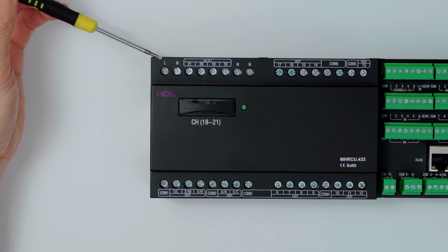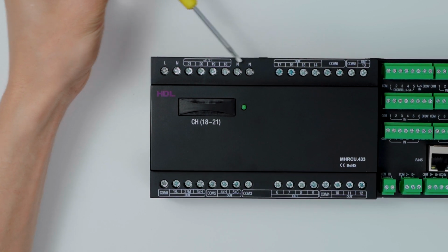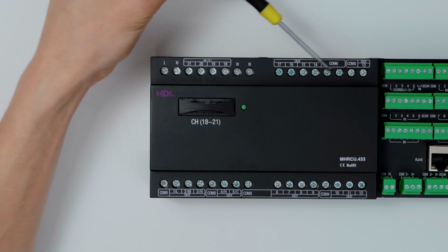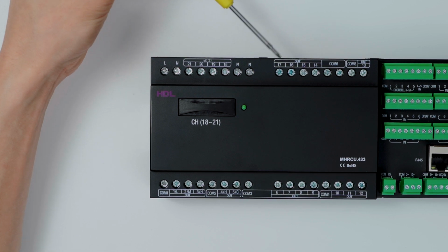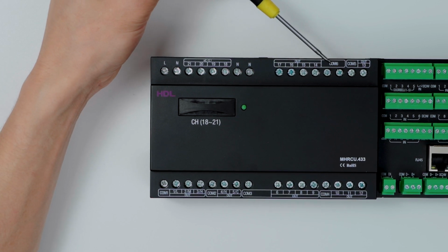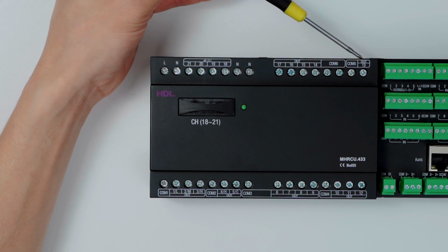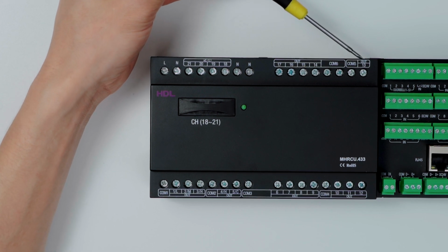LN is the input for mains power, live and neutral. The 3 neutral lines need to be combined, connected together. Special attention is needed for the out ports 14, 15, 16, and 17, as they are managed by COM6 and require a connection to the live wire for power supply. The COM5 interface also requires power supply for output 13.